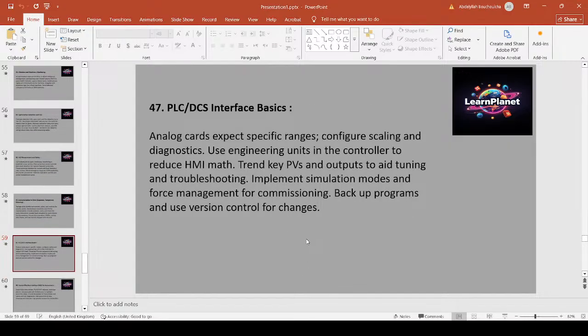PLC DCS interface basics. Analog card expects specific ranges. Configure scaling and diagnostics. Use engineering units in the controller to reduce HMI math. Trend PVs and outputs to aid tuning and troubleshooting. Implement simulation modes and force management for commissioning, back up programs, and use version control for change.